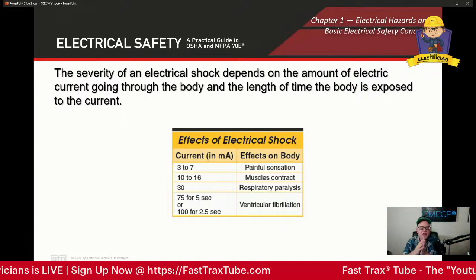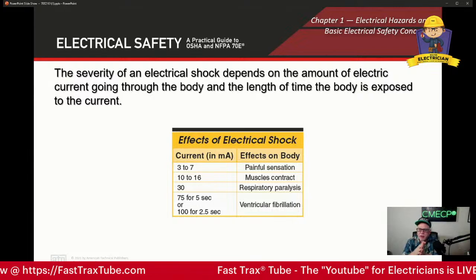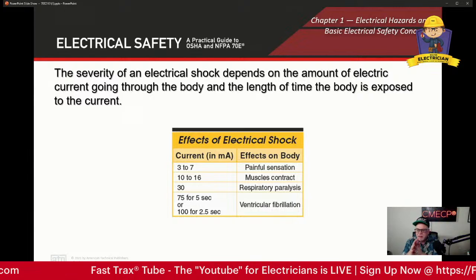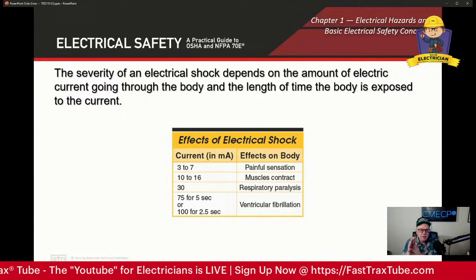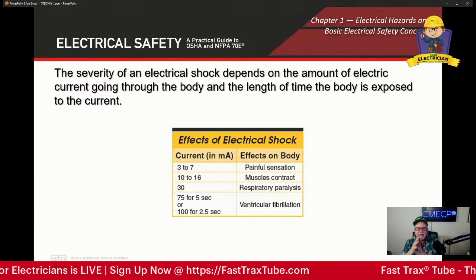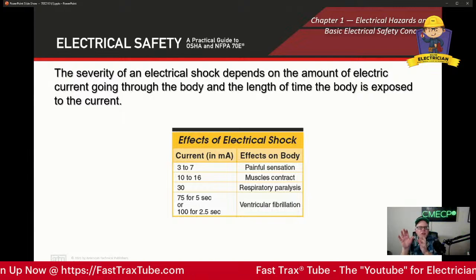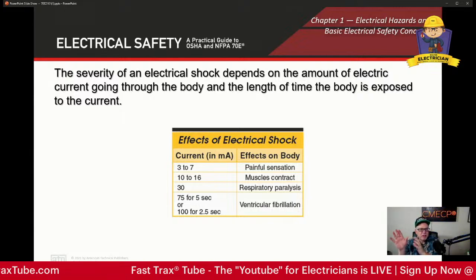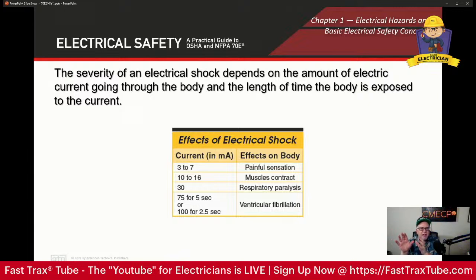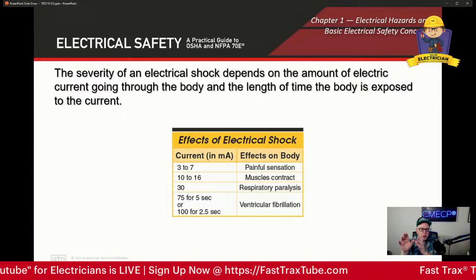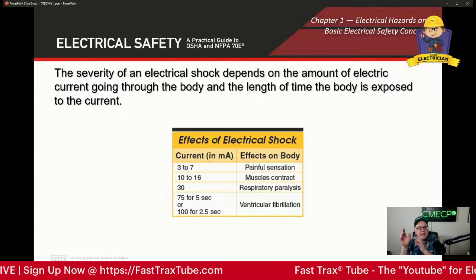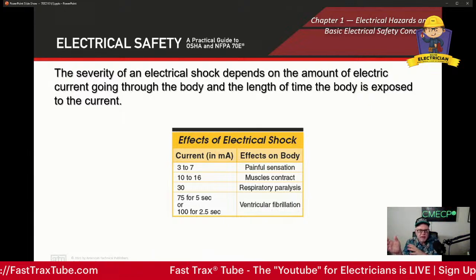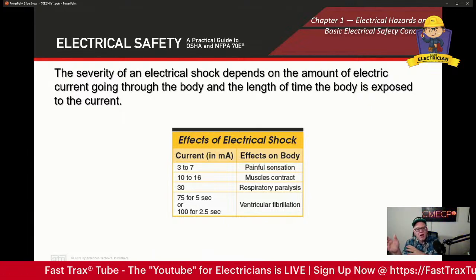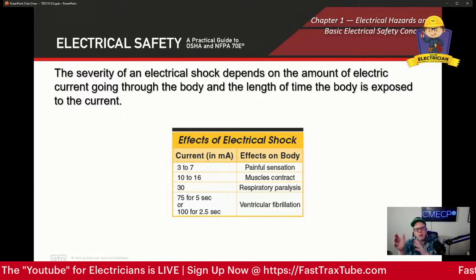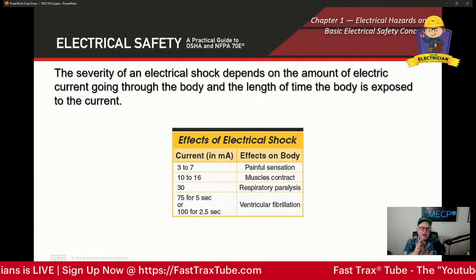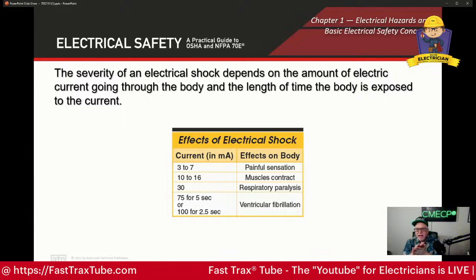All right, now let's talk about electric shock a little bit. Everybody's probably familiar with Charles Dalziel, he was basically the godfather of GFCI, right? So you look at this table and understand how simplistic it can be when you get shocked and what could happen. The severity of electric shock depends on the amount of electric current through the body and the length of time the body is exposed to that current. So the quicker the overcurrent device, the quicker the GFCI can shut down, the less exposure you have. And if you look at this chart, you're dealing in milliamps, a thousandth of an amp.